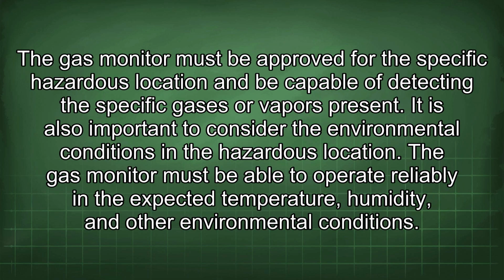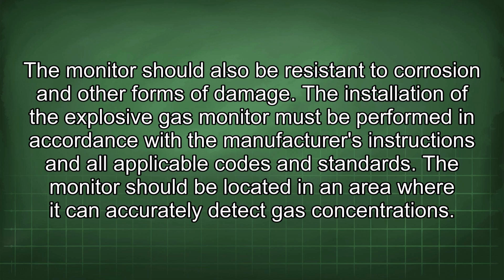The gas monitor must be approved for the specific hazardous location and be capable of detecting the specific gases or vapors present. It is also important to consider the environmental conditions in the hazardous location. The gas monitor must be able to operate reliably in the expected temperature, humidity, and other environmental conditions. The monitor should also be resistant to corrosion and other forms of damage.